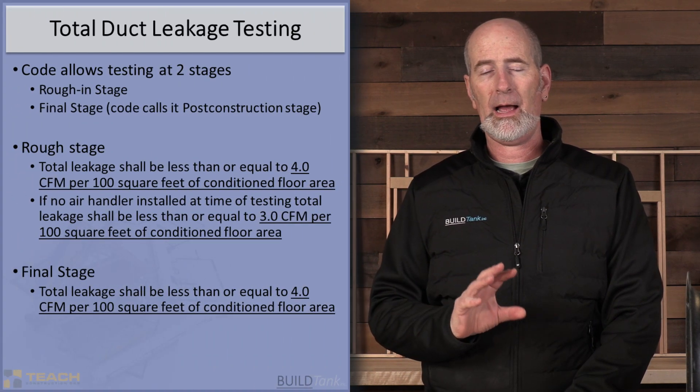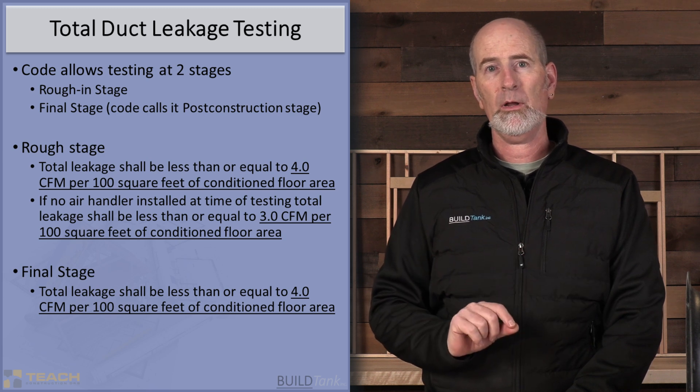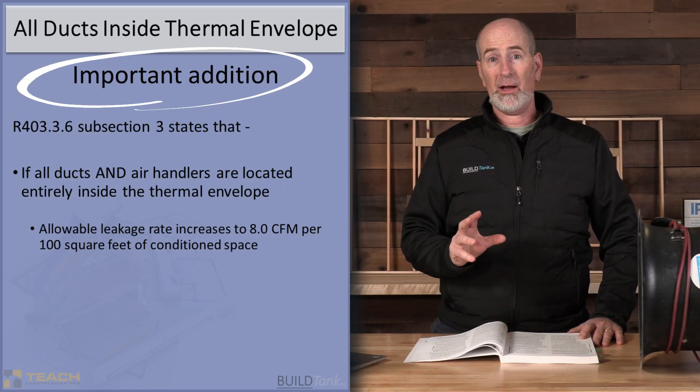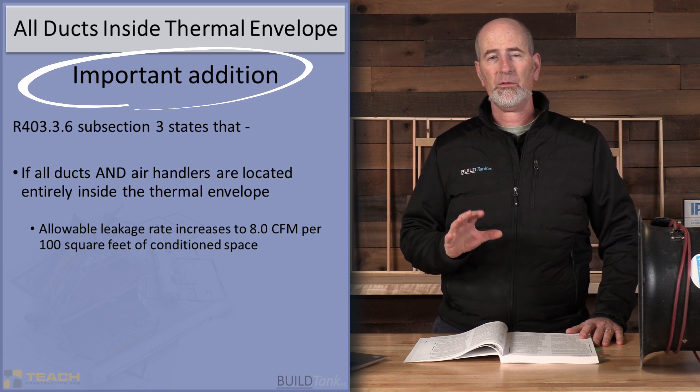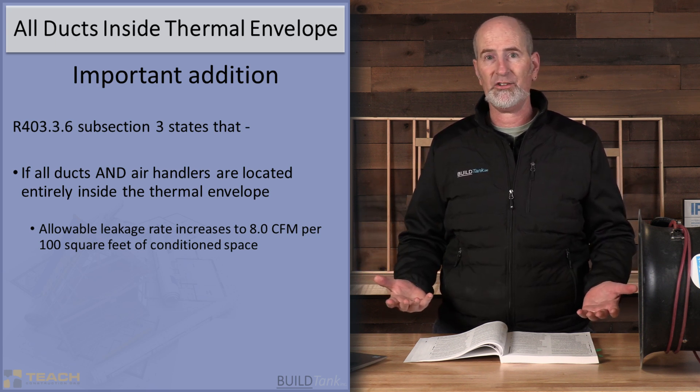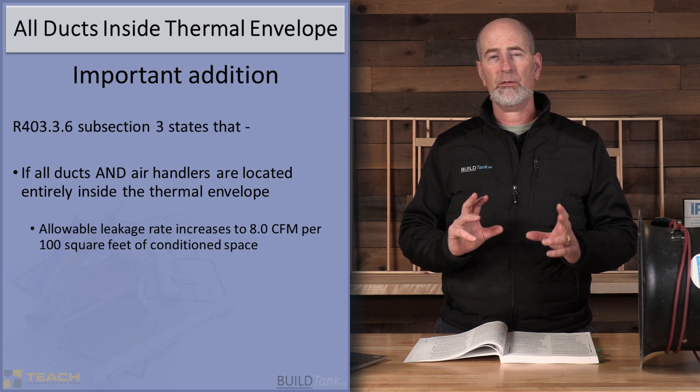You're allowed to test either at a rough stage of construction or a final stage of construction. The requirement is that the duct system can't leak more than 4 CFM per 100 square feet of conditioned floor area. Conditioned floor area is any floor area that's inside the building thermal envelope that is being conditioned. Unfinished space would still be calculated within the conditioned floor area — space inside a furnace room or a conditioned basement that's not finished would also be considered conditioned floor area.